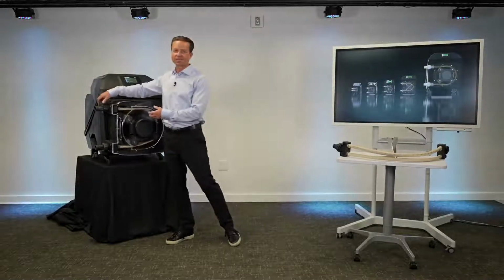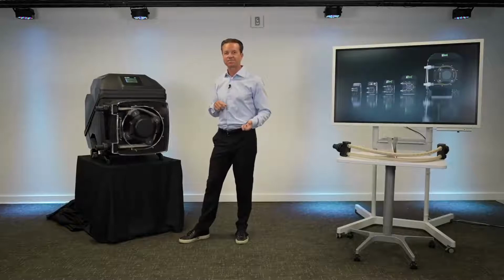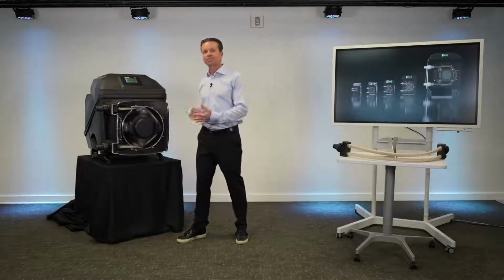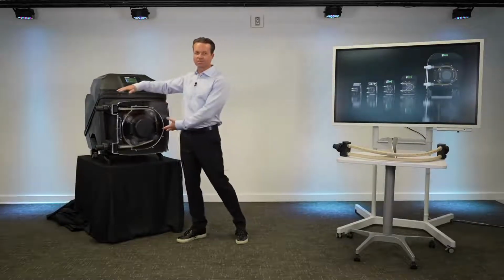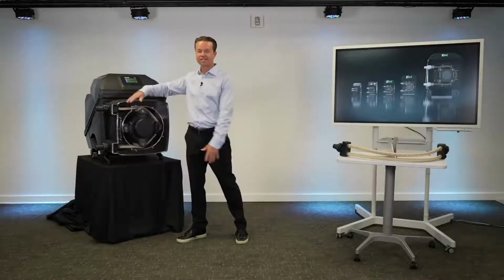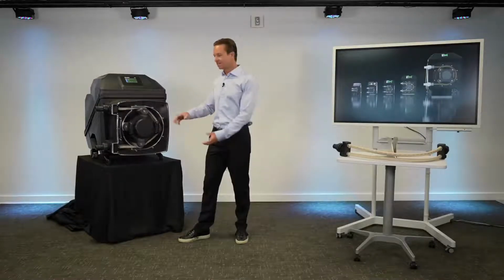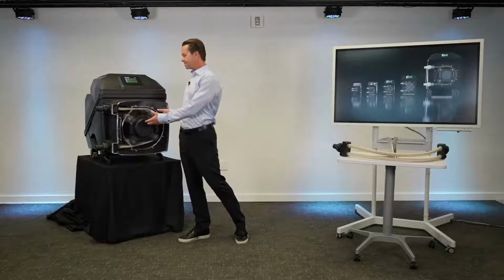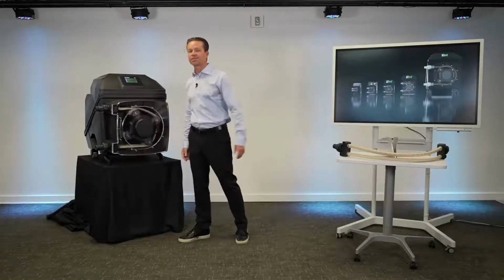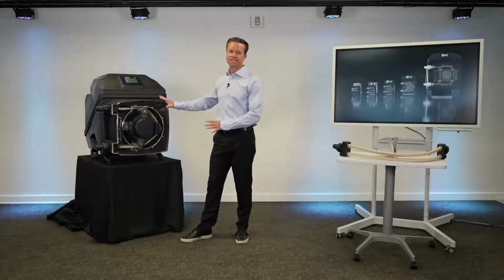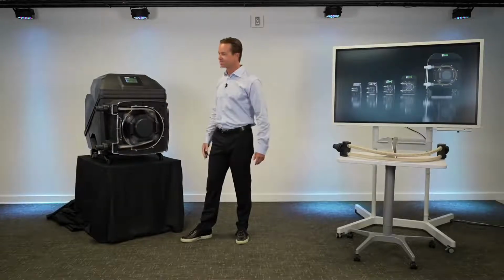Then you can easily, without force, remove the tubing, and basically reverse the procedure: place the tubing back in the pump head, replace the squeeze rollers, turn the locking ring clockwise to the right, and replace the pump head cover with the handles.